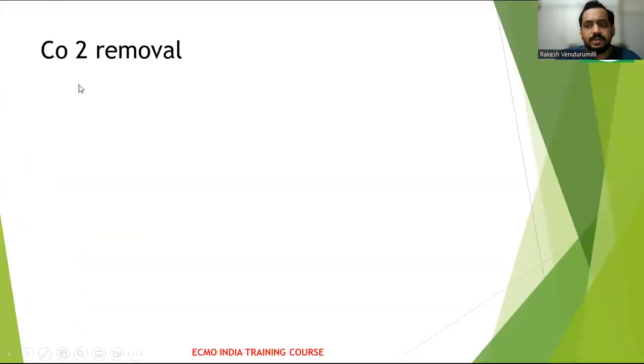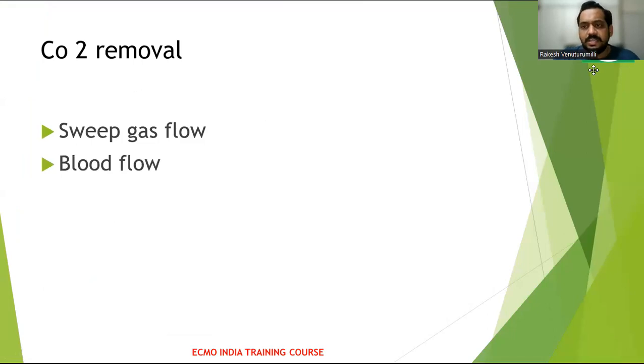Coming to carbon dioxide removal, let's see about the CO2 removal. The CO2 mainly depends upon your sweep gas flow and your blood flow. Any normally working oxygenator is capable of removing carbon dioxide when the blood flow to the sweep gas flow is from 1:1 to 1:2 ratios. More than 1:2, for example, if your blood flow is around 5 liters, the maximum allowable sweep gas flow is 10 liters. More than 10, it's not going to function. That is how the oxygenator is designed. So sweep gas flow is one thing which removes your carbon dioxide, and blood flow is another thing. You need to maintain the ratios.